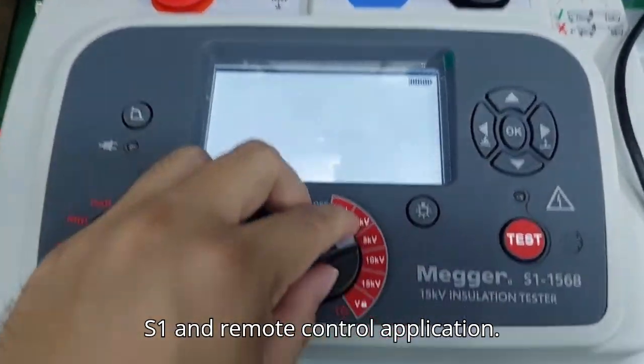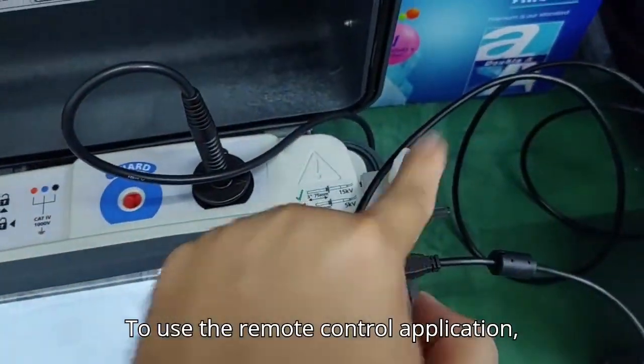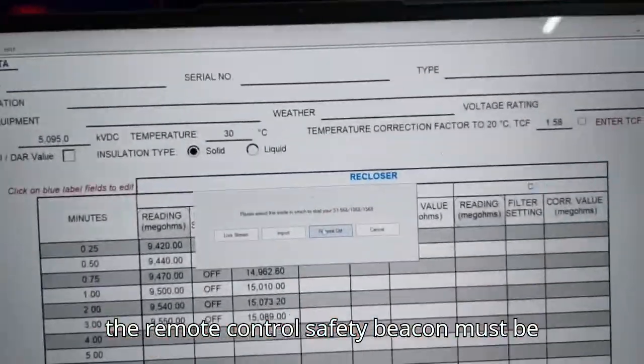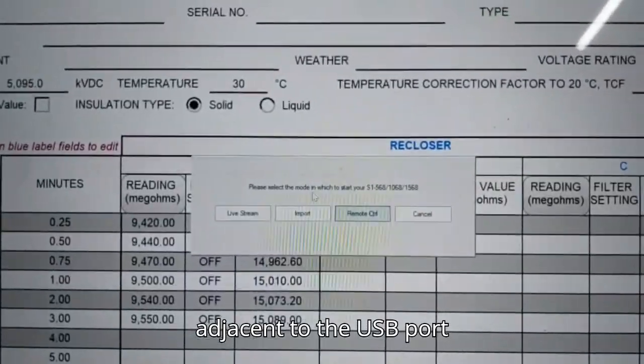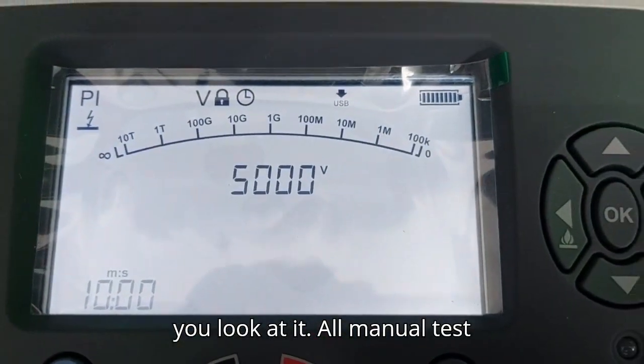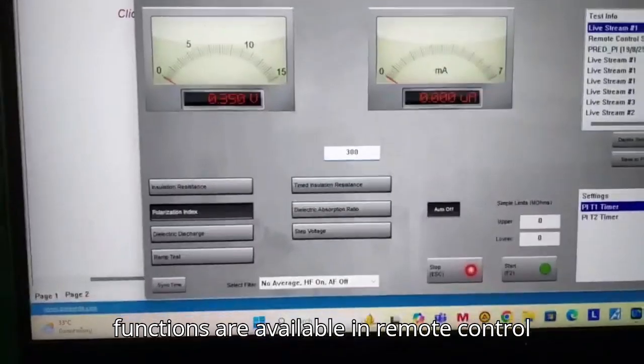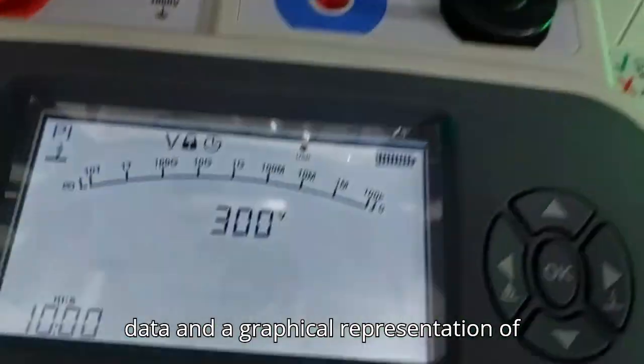To use the remote control application, the remote control safety beacon must be inserted into the nine pin socket found adjacent to the USB port on the right side of the instrument as you look at it. All manual test functions are available in remote control as well as real-time streaming of test data and a graphical representation of resistance, voltage and current in the top left window.